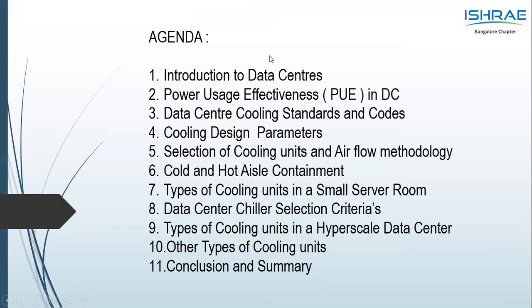The agenda for today is introduction to data center, power usage effectiveness, PUE, we'll look at that, data center cooling standards and codes, cooling design parameter, selection of the cooling units, airflow methodology, let's look at that. What are the different parameters to select a cooling unit? Cold aisle, hot aisle, containment, let's look at that. As we keep hearing on the containment, let's look at that.